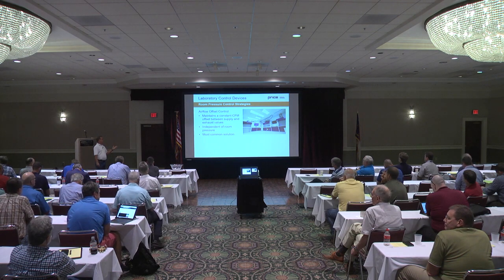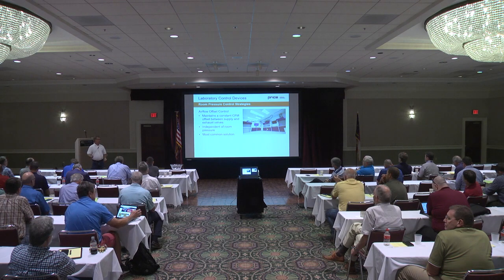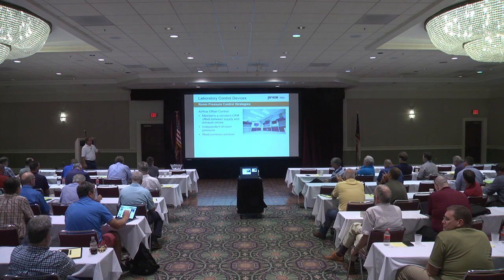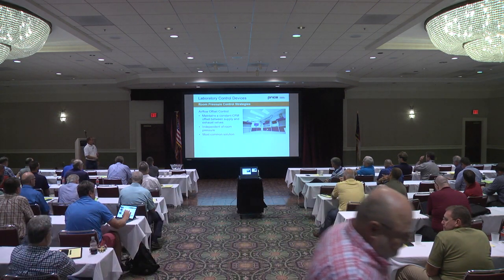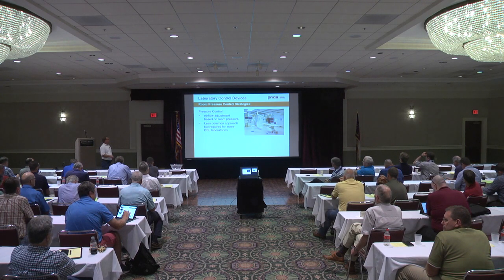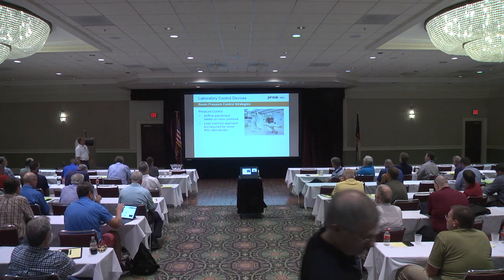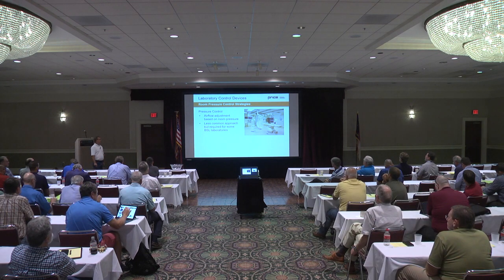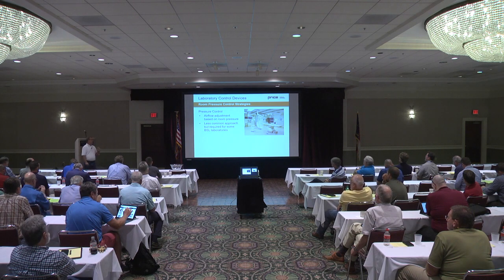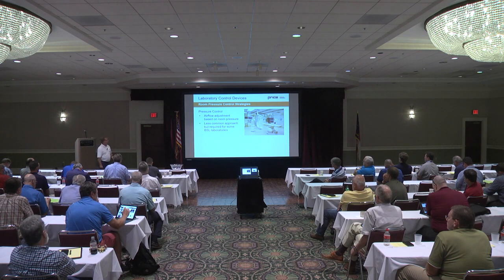You're not controlling off of room pressure, because as we know, open a door, leave the room, your pressure changes, so then you start moving your supply or exhaust to try and catch the pressure change. Where you maintain fixed offsets, you won't be changing the room due to a door opening or someone changing the space pressure. But other forms of pressure control strategies, where you would adjust the room pressure, maybe an operating space, BSL, the driving force for that control is the pressure, and you want to adjust it for a door opening, something changing, because you cannot allow any possible neutral situation due to a door opening.